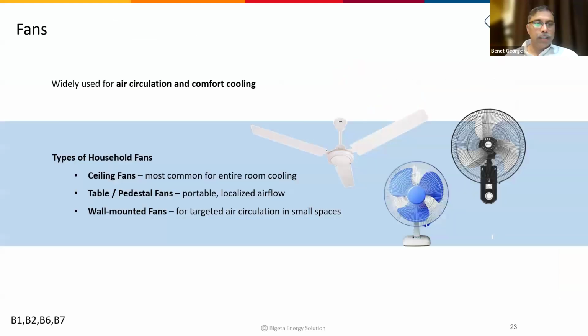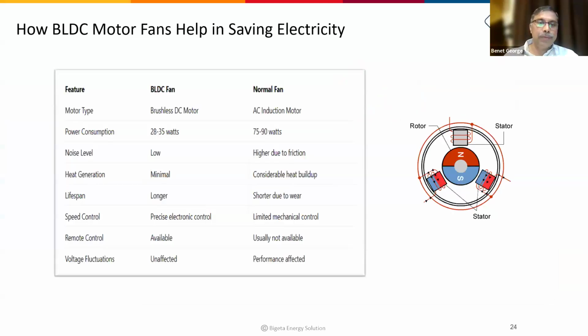Then one of the energy consuming equipment in campuses is fans. It can be ceiling fans, table fans, pedestal fans, or wall mounted fans. Typically the conventional fans use induction motors, and the present technology is the BLDC fan, which helps to reduce the energy consumption. So this gives a comparison between a BLDC fan and a normal fan. A BLDC fan typically consumes 28 to 35 watt based on the speed, but a normal induction motor fan typically consumes between 75 and 90 watt.